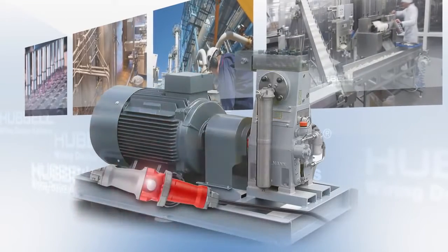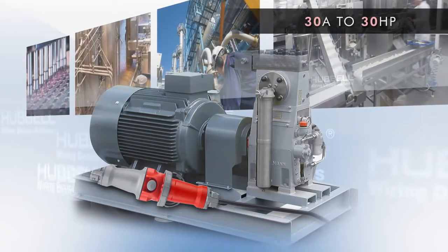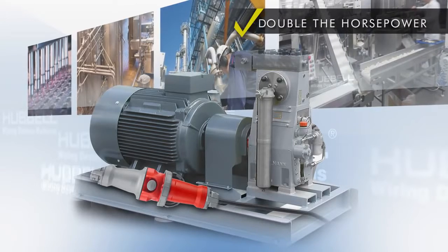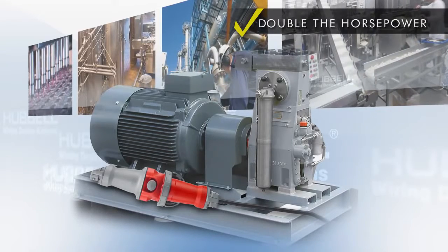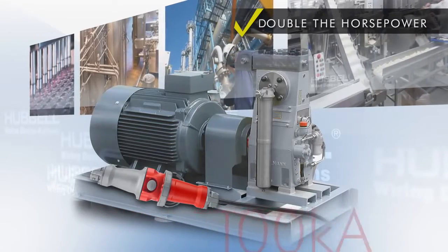The Advantage Series has increased the maximum horsepower rating of a 30-amp switched connector to 30 horsepower — a new industry benchmark, doubling the previous. In addition, it has a short-circuit current rating of 100 kA when used with a Class G fuse.